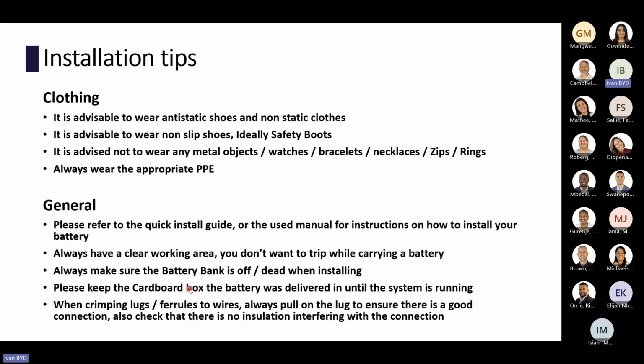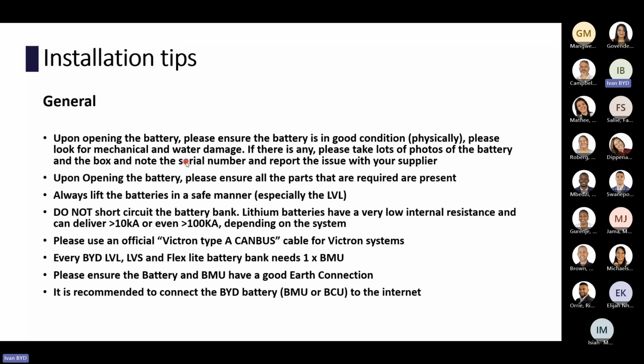And also please ensure that all your lugs are tight. I have come across a couple of installations where a loose cable has caused an issue. So it's always a good idea, before you turn on your battery bank, to go around the whole battery bank and tighten everything. When opening the battery, please ensure the battery is in good condition physically, and look for any mechanical and water damage. If there are any issues, please take photos and the serial number. Please always lift the batteries in a safe manner.